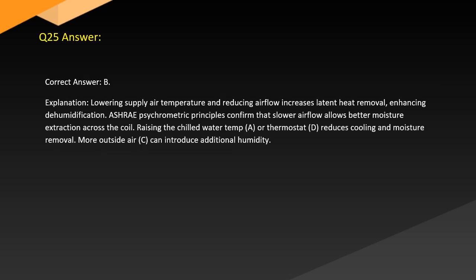Answer. Correct answer: B. Explanation. Lowering supply air temperature and reducing airflow increases latent heat removal, enhancing dehumidification. HVAC psychrometric principles confirm that slower airflow allows better moisture extraction across the coil. Raising the chilled water temperature (A) or thermostat (D) reduces cooling and moisture removal. More outside air (C) can introduce additional humidity.